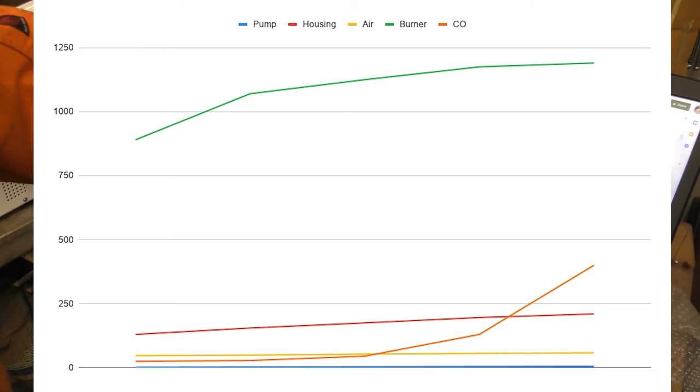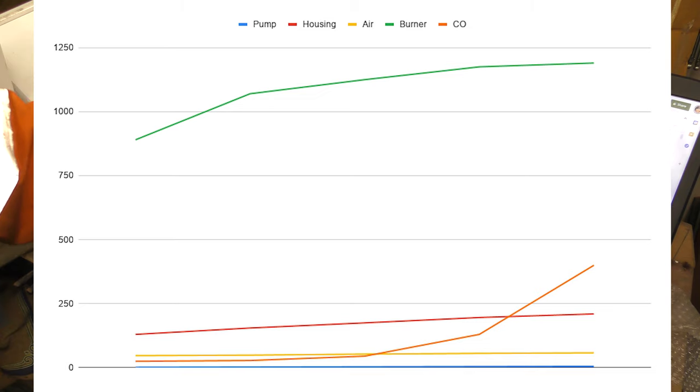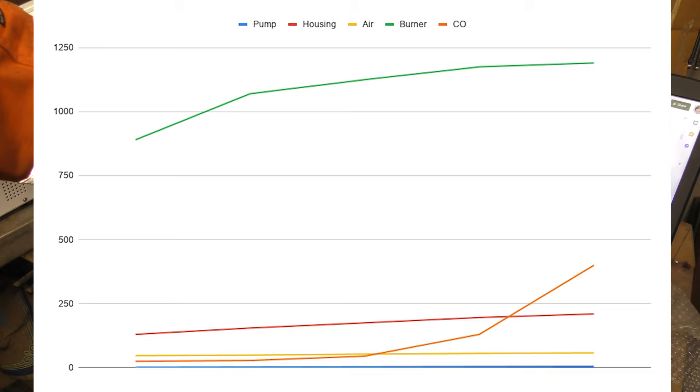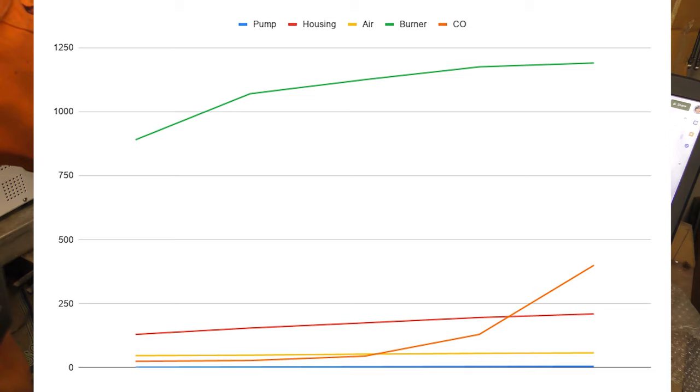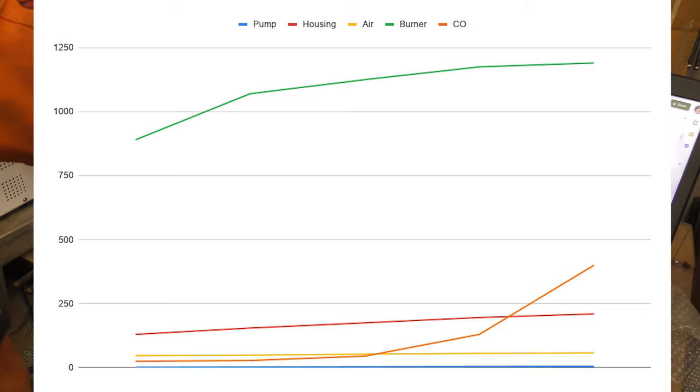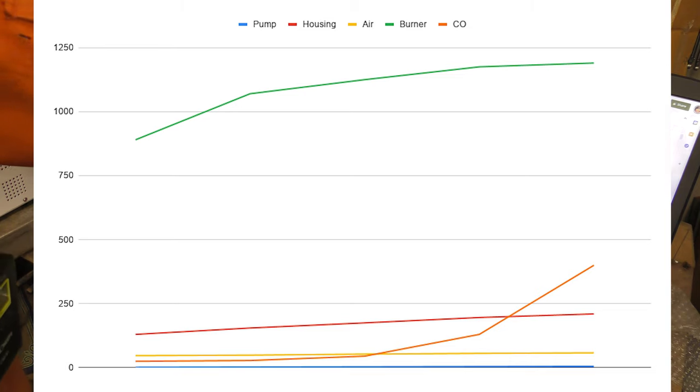So looking at the graph, you're looking at like 850 to 900 as maybe the bottom end. You never want to take the temperature below that, it gets too low. I have noticed that on starting, you get that humping noise that it only does when the burn chamber temperature is below 800. Then it may be a combination of the fan speed picking up as well as the fuel speed picking up. But when it gets to that 800 to 900 degrees, the noise goes away and it starts to run normally.